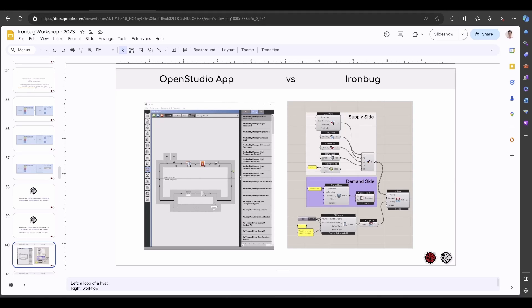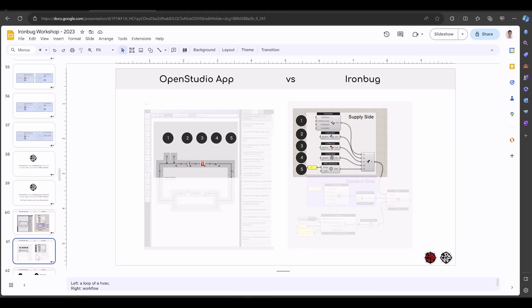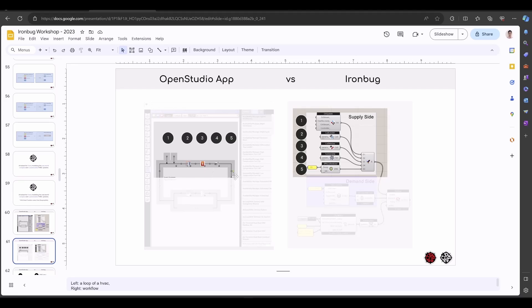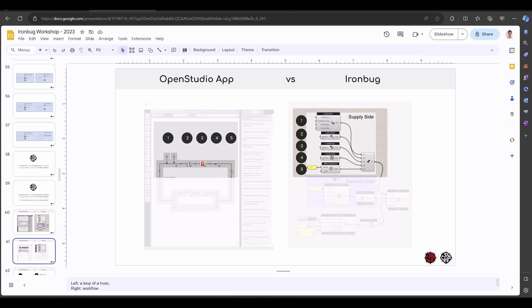Now let's compare OpenStudio application and the IronBug interface. Let's just look at the supply side. On the left is the application. You can see five components from the air loop system: cooling coil, heat coil, fan, and the setpoint manager. On the right side, the five elements are layered vertically. How each element connected is from the top to the bottom.